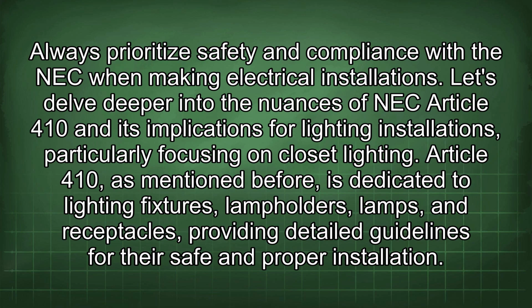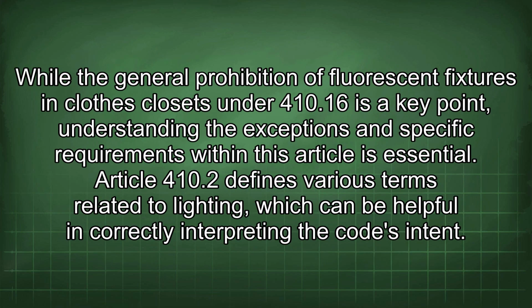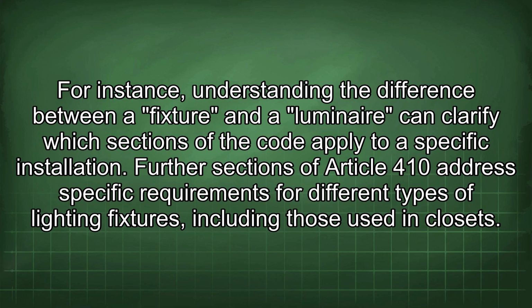Let's delve deeper into the nuances of NEC Article 410 and its implications for lighting installations, particularly focusing on closet lighting. Article 410, as mentioned before, is dedicated to lighting fixtures, lamp holders, lamps, and receptacles, providing detailed guidelines for their safe and proper installation. While the general prohibition of fluorescent fixtures in clothes closets under 410.16 is a key point, understanding the exceptions and specific requirements within this article is essential. Article 410.2 defines various terms related to lighting, which can be helpful in correctly interpreting the code's intent. For instance, understanding the difference between a fixture and a luminaire can clarify which sections of the code apply to a specific installation.